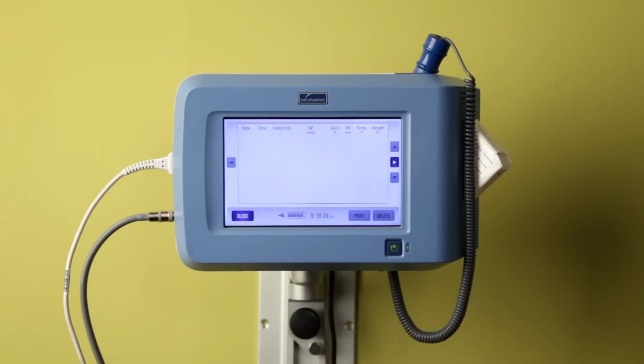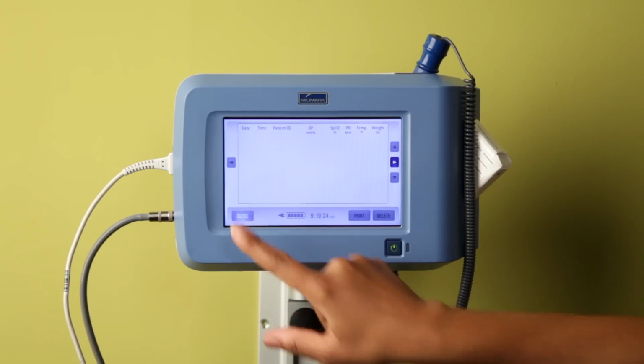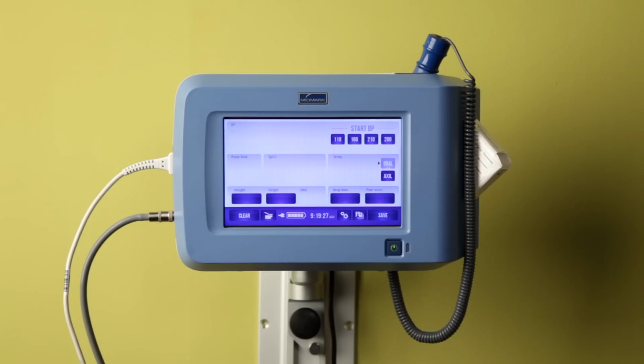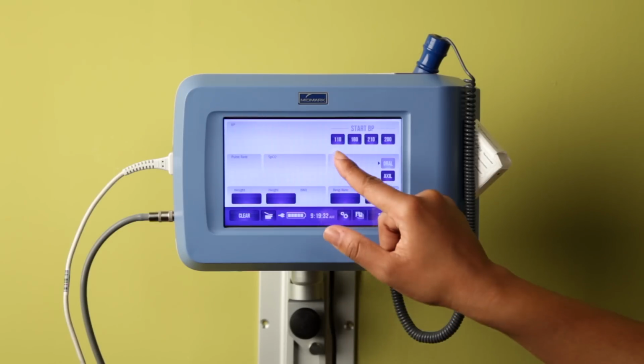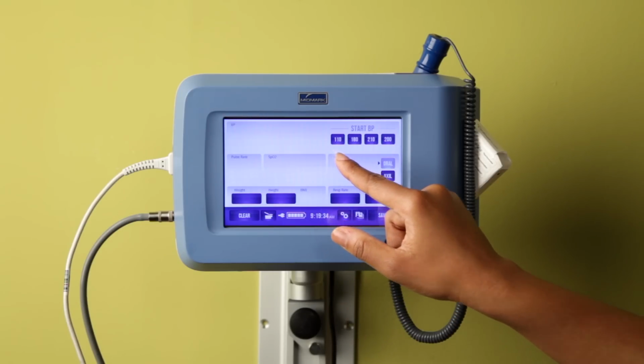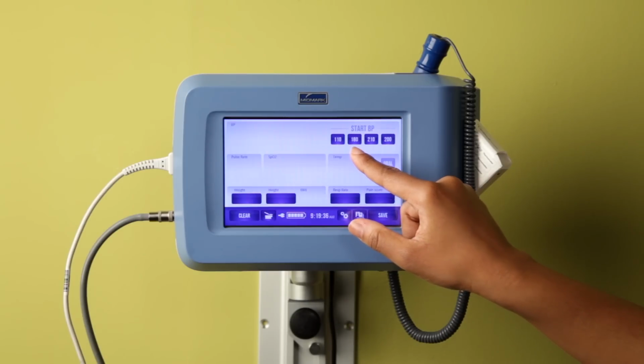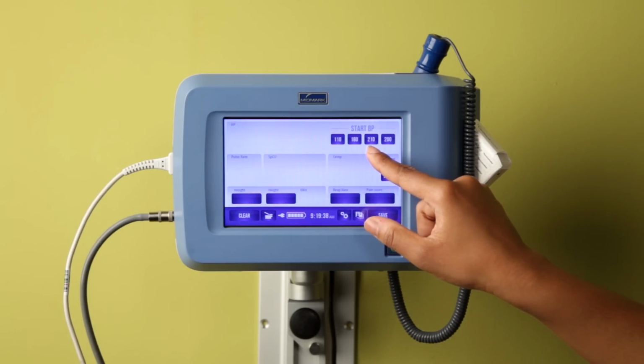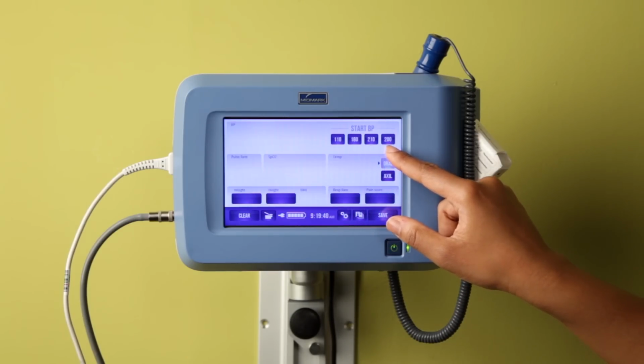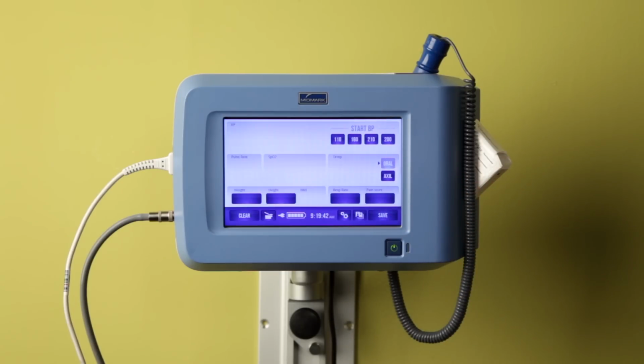To initiate a blood pressure measurement, make sure IQvitals is in the main testing screen. There are 4 blood pressure setting buttons to choose from. These can be preset to pressure settings of the user's choice. Ideally, the initial inflation cuff pressure should be about 30 millimeters of mercury above the patient's systolic pressure. Using a higher pressure may cause the patient unnecessary discomfort, while choosing a pressure that's too low may cause the device to reinflate the cuff in order to obtain a systolic pressure.